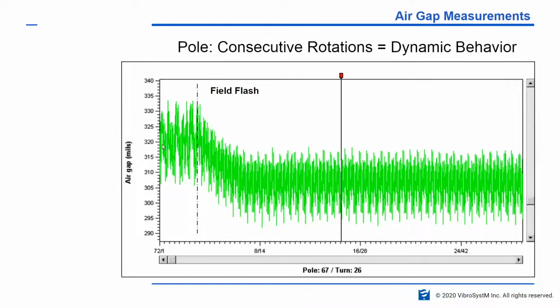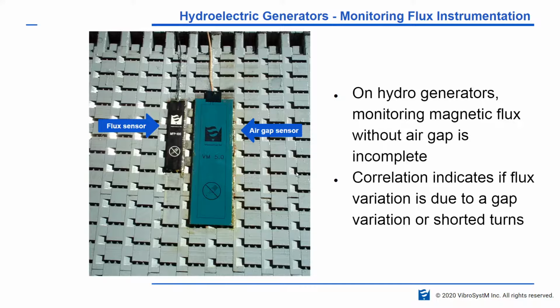This is an example of an air gap sensor looking at what happens to the air gap when the rotor is energized. And you can see there's a noticeable decrease in air gap, and that is usually caused by the sudden expansion of the rotor and the sudden contraction of the stator. So the movement of both create this decrease in air gap. Okay.